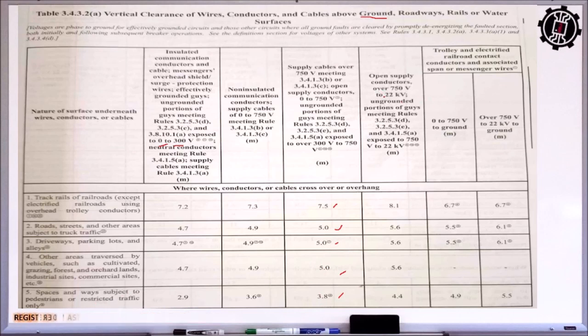Open supply conductors over 750 to 22 kilovolts. So ito na yung lalagpas na ng 750. So if dadaan siya sa isang train, 8.1 meters. All driveways, no, subject to heavy to moderate traffic, that is 5.6 meters. Kapag light traffic, 4.4 meters. So trolley and electrified railroad contact conductors and spans or wires. So this is for the mga wires ng ating mga train, no? Yung mga supply conductors for the railroad.